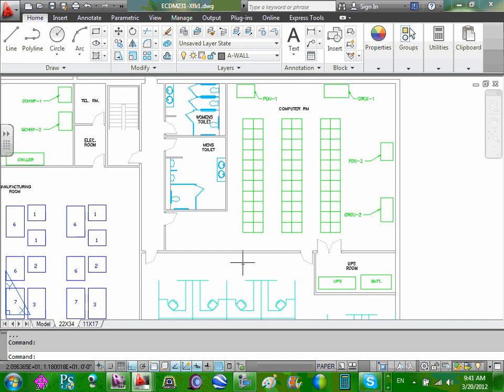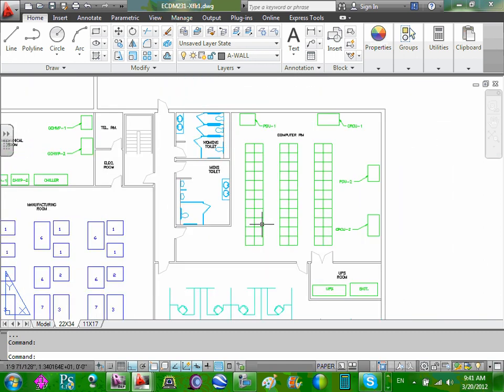We had complete 2N redundancy to the server. So I could have lost my whip, I could have lost the PDU, I could have lost my UPS, and all of the servers in that room would continue to be powered by their surviving power supply. Think of it as 2 cords to the one server. Let's say it's a 600-watt load at that one individual server. Each cord is carrying 300 watts because they both have a little power supply and they feed a common DC bus within that server. I unplug one cord, the other cord is now carrying 600 watts, and that DC bus didn't skip a beat. So we're maintaining power at that server if we lose a cord. And then upstream, we're adding reliability by having 2 PDUs, so if a PDU goes down, all the equipment would still survive because the other PDU is hot.